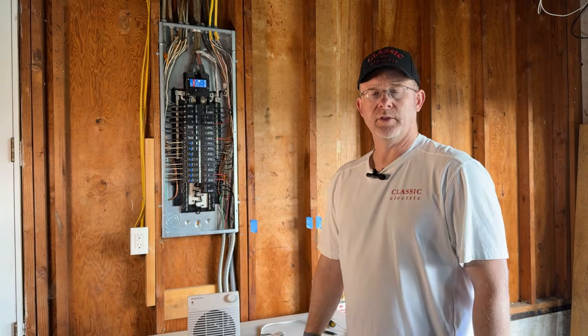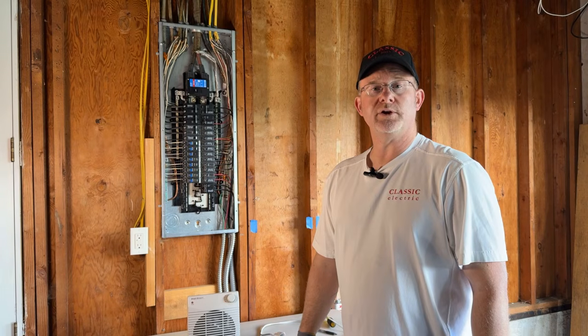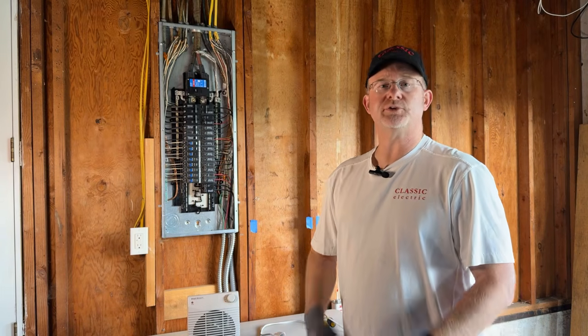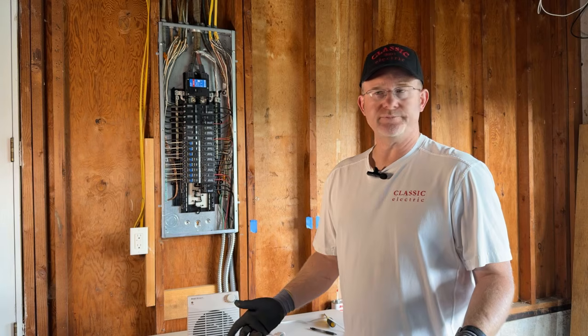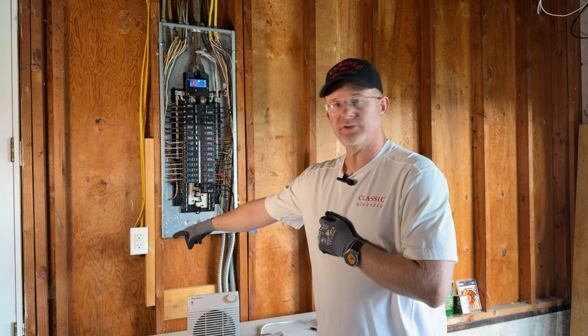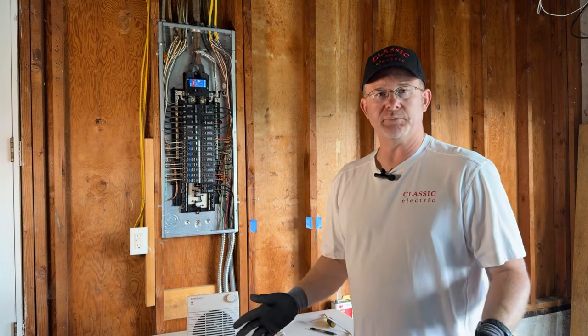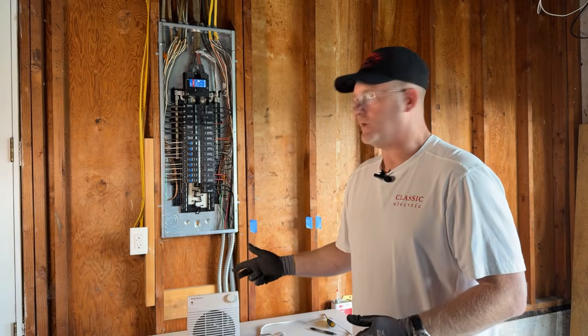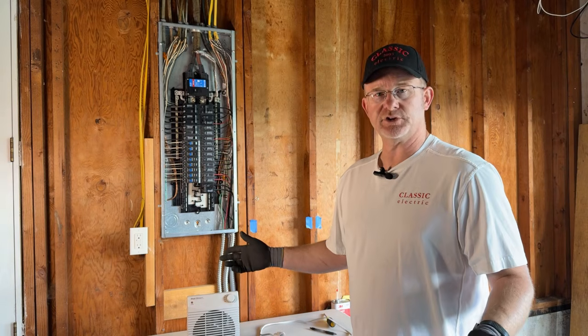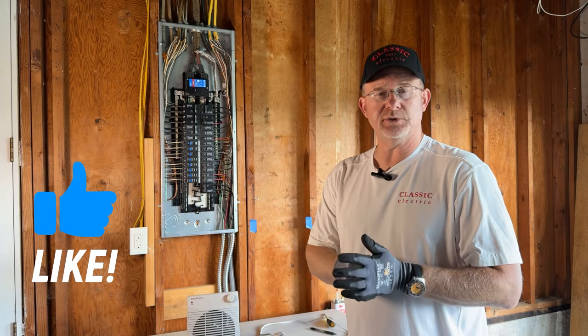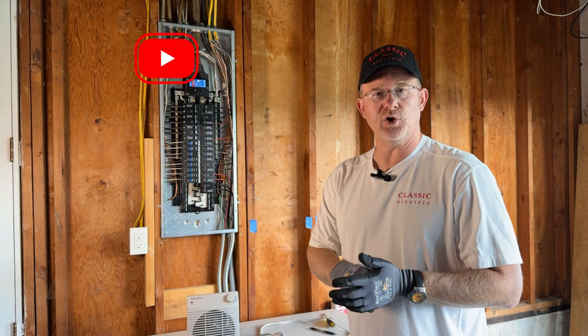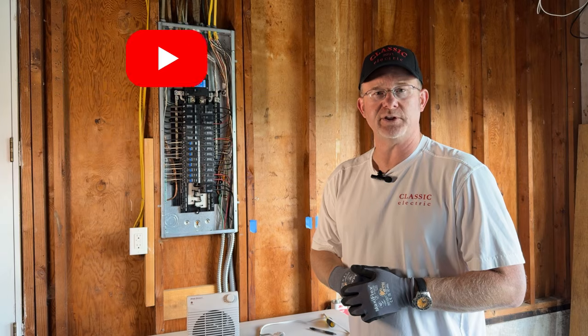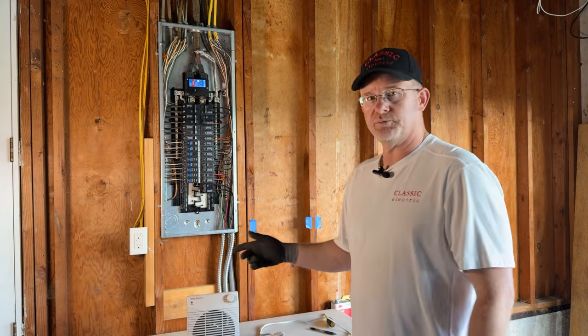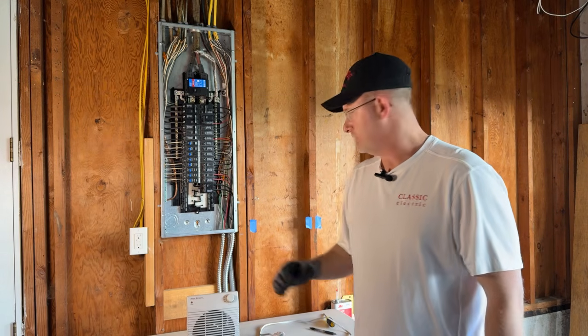Okay, so the whole point of arc fault breakers is to protect the structure from burning down. GFCIs with the test buttons were to protect people, period. Arc fault breakers are to protect the structure, which is exactly why you want to make sure you have nice tight connections, because the cause of most fires in homes are loose connections. And 10 times hotter than the face of the sun will definitely do that.